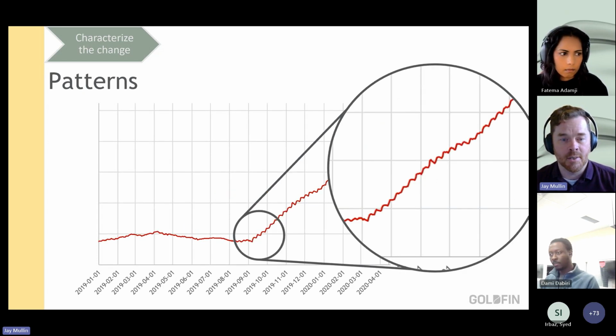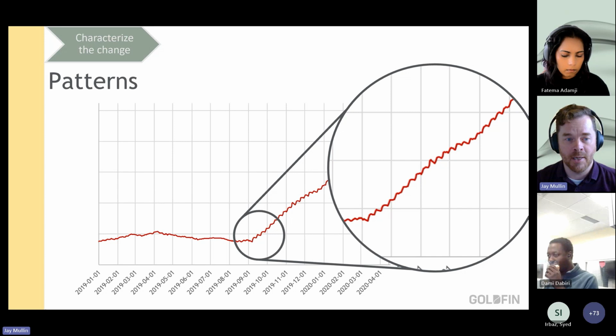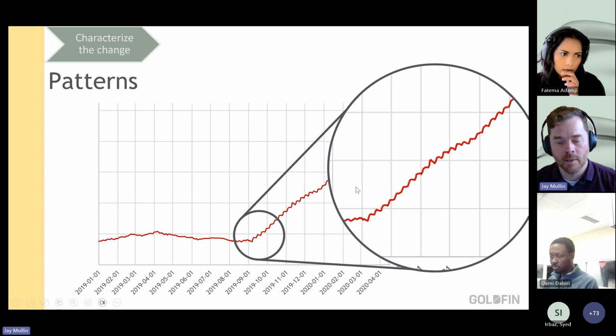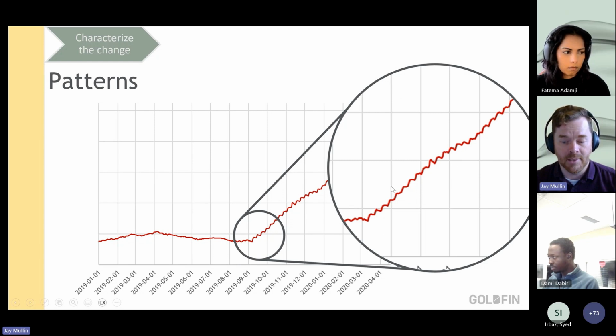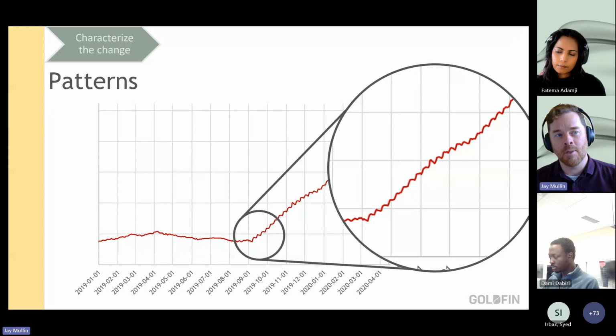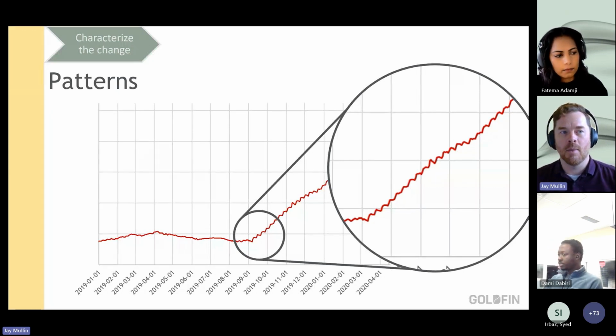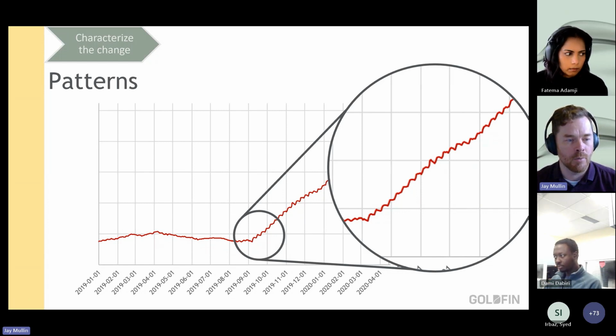The next part of characterization is looking for patterns in it. These patterns can also give us some more information. If you have a daily model, there might be a weekday weekend pattern like the one we see here, where it slopes up on weekends, like Saturdays and Sundays, but the slope is flat or even negative during the week. This is a pretty consistent pattern going on through this time. That can tell us something different is happening on weekends than is happening during the week, so maybe there's something to do with BAS scheduling or things like that.